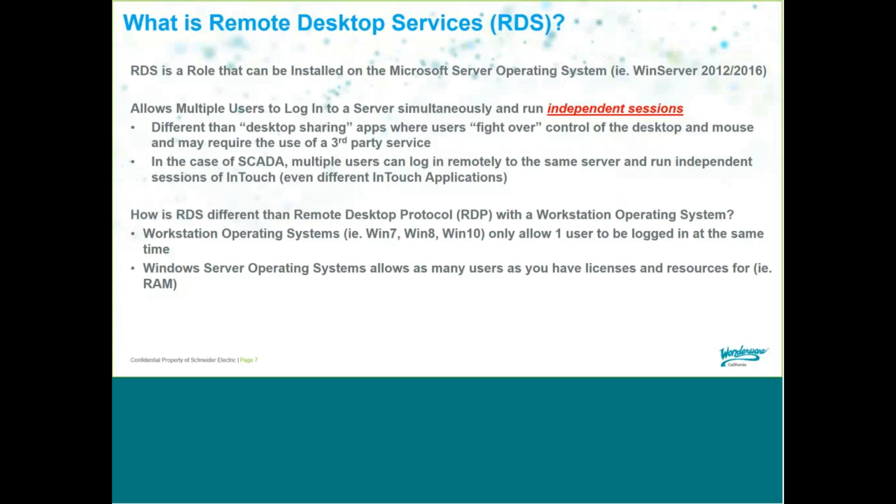The other benefit is that you can run multiple different InTouch applications on the server, and so people that are remoting in can access different InTouch applications. So somebody might just need to see the water plant, somebody might need to see the wastewater plant, somebody might need a supervisor type application, somebody might need a full operator application. So you can have different InTouch applications running on the same server, and multiple users can access whichever InTouch application is appropriate for them.